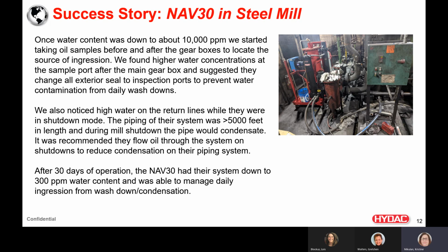After 30 days in operation, the NAV30 had their system down to 300 parts per million water content, and we were able to manage the daily ingression from washdown and condensation.